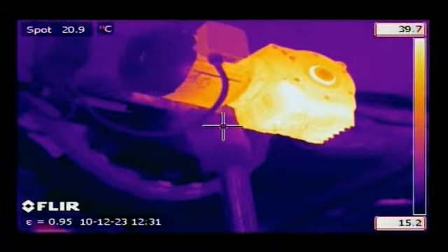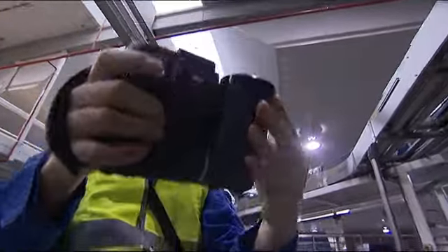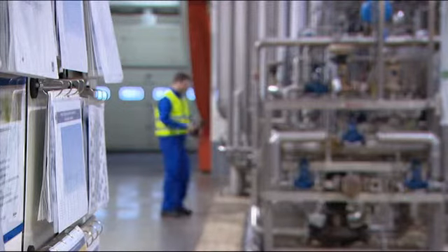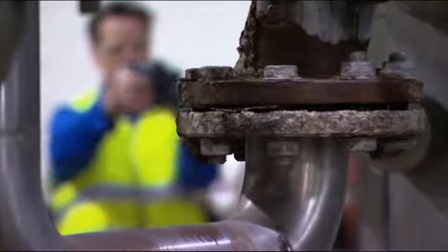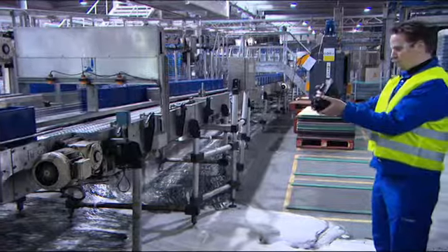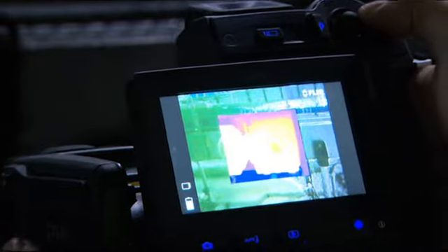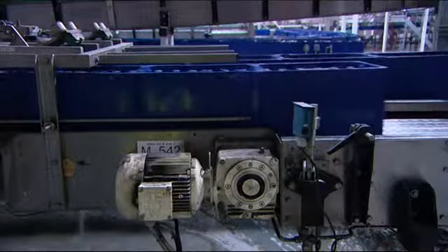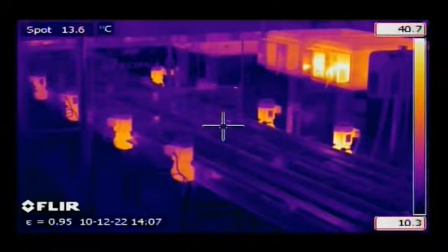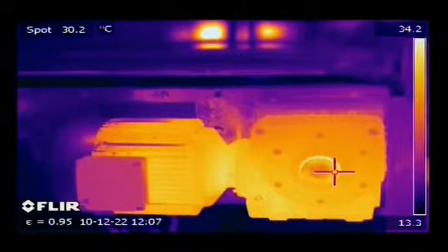Motors are also widely inspected with thermal imaging cameras. Motors can be observed for brush contact wear and armature shorts, both of which typically produce excess heat, but not necessarily vibration, prior to failure. Thermal imaging gives a full overview and allows to compare the temperature of different motors. When necessary, further examination of the overheating motor can be done. Most FLIR cameras are equipped with a laser pointer which eliminates the tendency to finger point in dangerous areas.